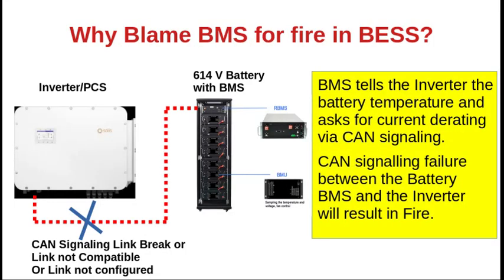Why blame BMS for fire in the BESS? In the picture, you see there is a link between the inverter and the master BMS of the battery. This link is a CAN signaling link. If it is failed for any one of the three reasons: there is a mechanical link break, or the link is not compatible in software or in the signaling, that is, the inverter is not compatible to the battery, or even if they are compatible, the person who installs has not configured both sides of the link properly, then the link will not be operational. If the link is not operational, it can lead to fire in the BESS.